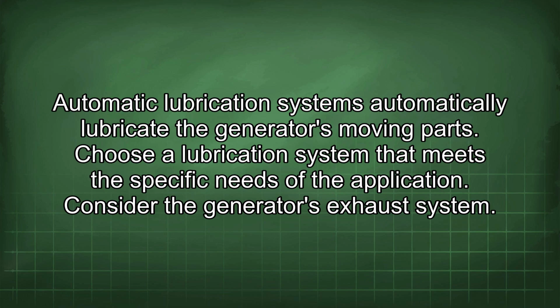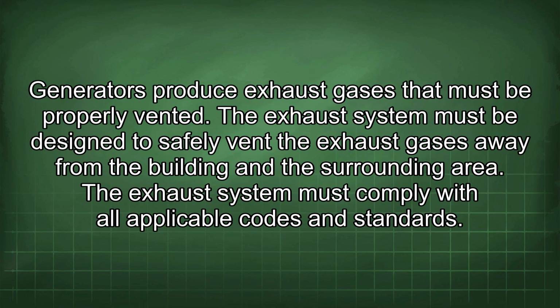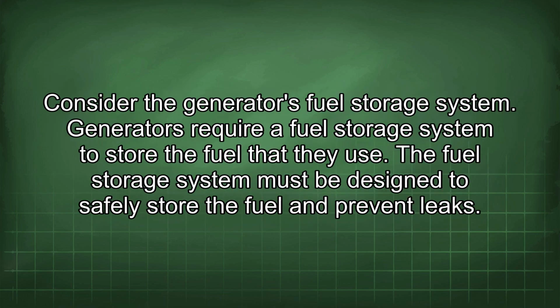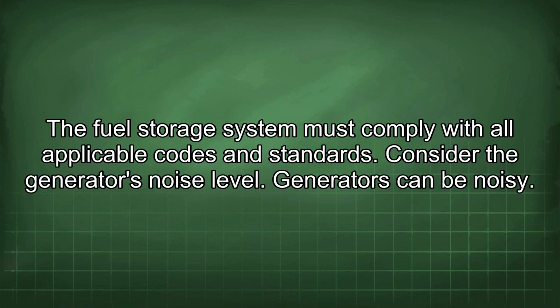Consider the generator's exhaust system. Generators produce exhaust gases that must be properly vented. The exhaust system must be designed to safely vent the exhaust gases away from the building and the surrounding area. The exhaust system must comply with all applicable codes and standards. Consider the generator's fuel storage system. Generators require a fuel storage system to store the fuel that they use. The fuel storage system must be designed to safely store the fuel and prevent leaks. The fuel storage system must comply with all applicable codes and standards.